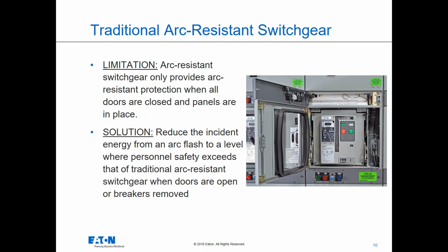Maybe you're doing routine maintenance and that maintenance requires the breakers be removed for primary injection, but the owner wants to continue operating the switchgear. Well, the minute that bolted and latched compartment door is opened for that breaker, now that equipment is not arc resistant anymore. And whoever's operating in front of the gear needs to be wearing appropriate PPE for the arc levels that are present if we consider the gear to be non-arc.